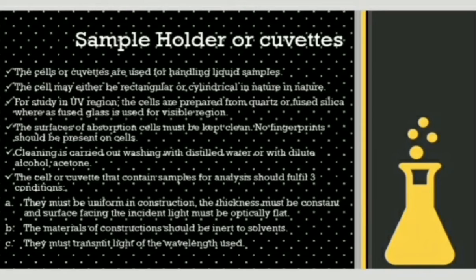The sample holder or cuvettes are used for handling liquid samples. Cells may be rectangular or cylindrical. For the UV region, cells are prepared from quartz or fused silica, whereas fused glass is used for the visible region. The surfaces of absorption cells must be kept clean with no fingerprints, and cleaning is carried out by washing with distilled water or dilute alcohol acetone. Cuvettes must fulfill three conditions: uniform construction, constant thickness with optically flat surfaces facing the incident light, and materials inert to solvents that transmit light of the required wavelength.